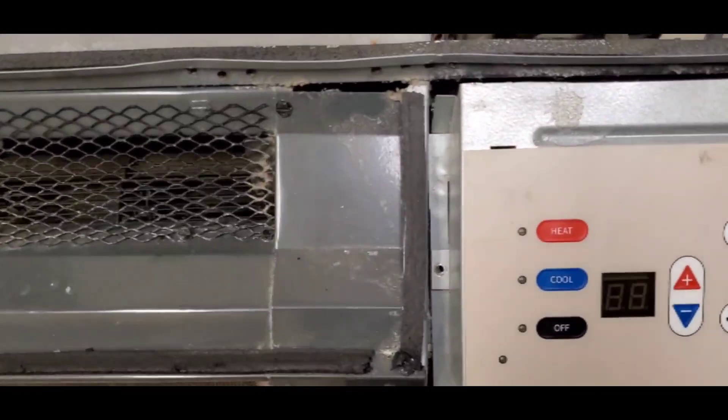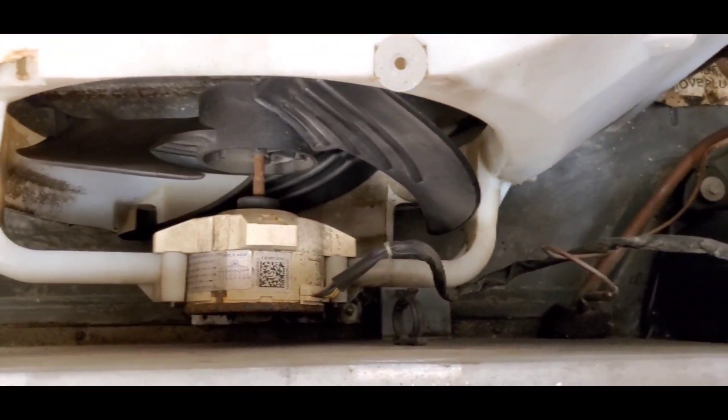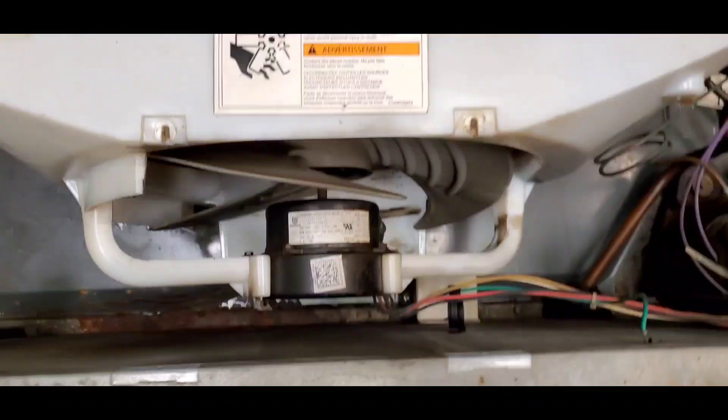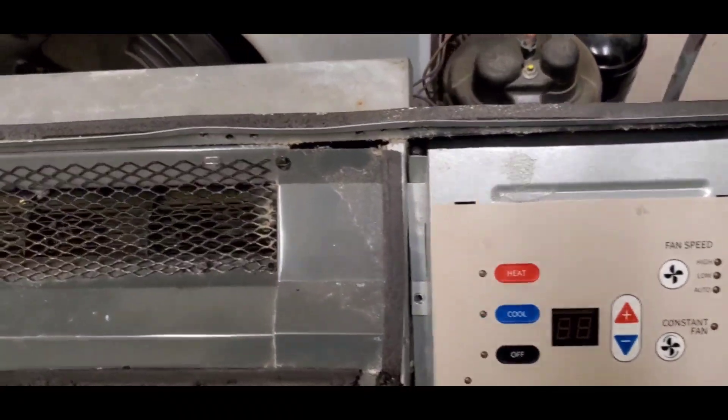I have an Amana PTAC unit with a noisy DC condenser motor. I don't have that motor in stock, but this property really needs this unit, so I'll be using a regular motor from another unit that's not working so I can get this one up and running.